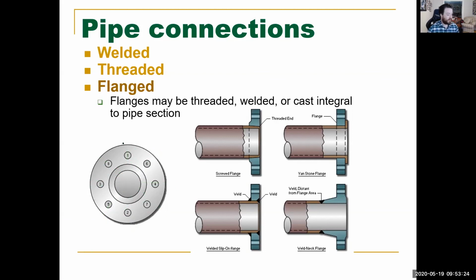And the reason is that if you're bolting something down and you have your two flanges together, these are my two sides of my flanges. If you bolt the top down, the top's going to be pressed together, and then you're just going to have a leak coming out of the bottom. The same thing goes for any other spot. And you don't want to be cranking down on bolt number one up here, and then when you go to number two, it's going to be an inch out. Same problem's going to happen, even if you stay with that star pattern.